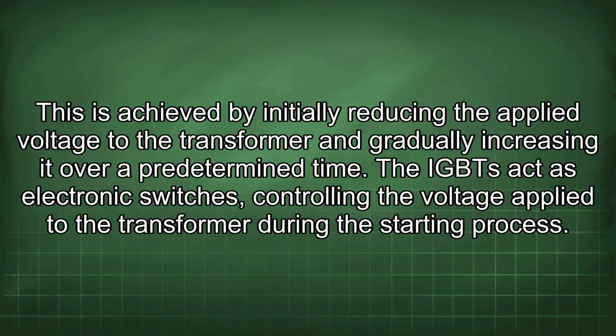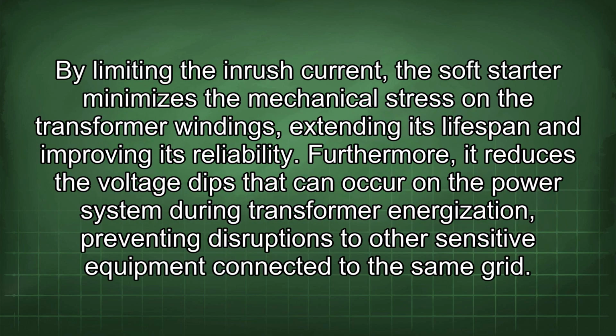This is achieved by initially reducing the applied voltage to the transformer and gradually increasing it over a predetermined time. The IGBTs act as electronic switches, controlling the voltage applied to the transformer during the starting process. By limiting the inrush current, the soft starter minimizes the mechanical stress on the transformer windings, extending its lifespan and improving its reliability. Furthermore, it reduces the voltage dips that can occur on the power system during transformer energization, preventing disruptions to other sensitive equipment connected to the same grid.